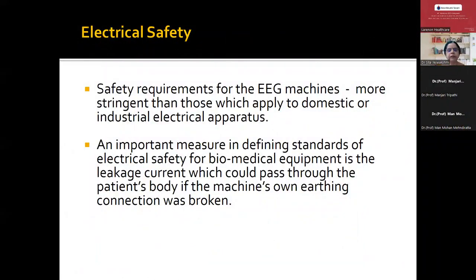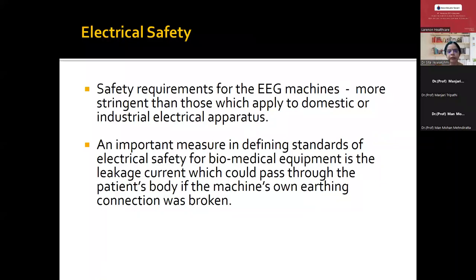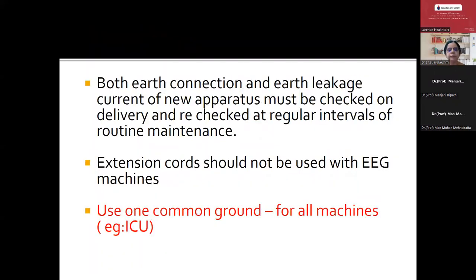The last part is electrical safety of the machine — very important because we do see accidents happening in EEG labs. It is important to define standards of electrical safety for biomedical equipment and to make sure there is no leakage of current which can pass through the patient's body if the machine's earthing connection is broken. Earthing is very important whenever an EEG lab is established. Extension cords should never be used along with EEG machines. Whenever using the EEG machine in ICUs, make sure there is only one common ground for all the machines.